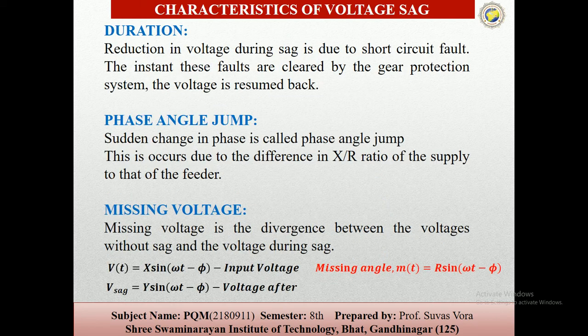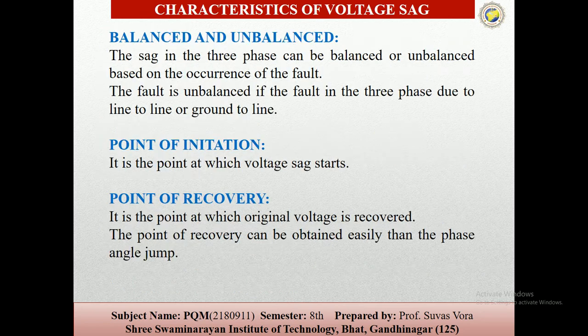The reduction in voltage during the sag is due to the short circuit fault. Then the phase angle jump is the sudden change in the phase, and the difference is the X by R ratio. Then missing voltage is the divergence between the voltage without sag and during the sag. Then balanced and unbalanced conditions, we know what balanced and unbalanced conditions are, then point of initiation and point of recovery.